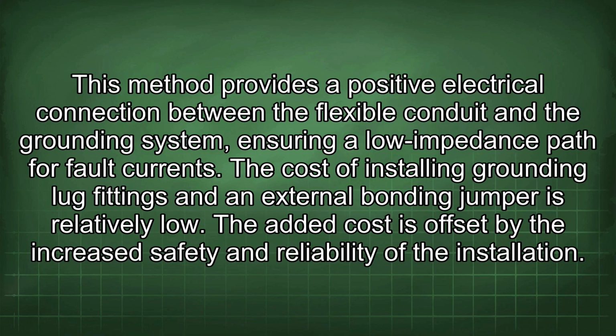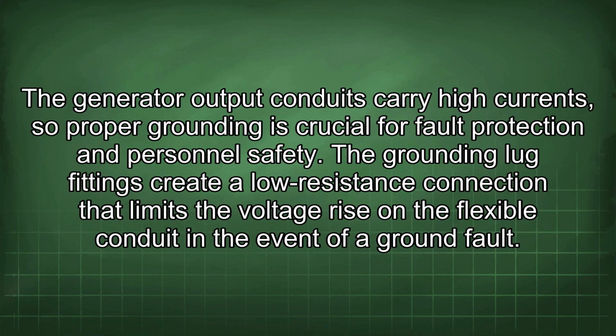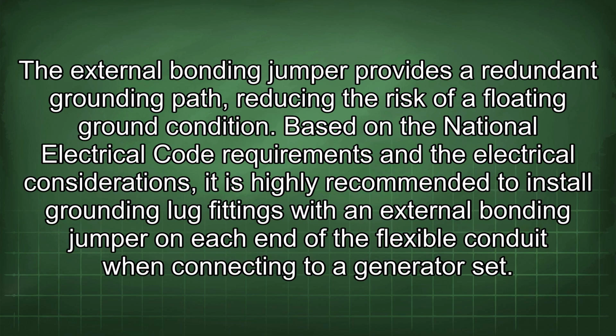This method provides a positive electrical connection between the flexible conduit and the grounding system, ensuring a low impedance path for fault currents. The cost of installing grounding lug fittings and an external bonding jumper is relatively low. The added cost is offset by the increased safety and reliability of the installation. The generator output conduits carry high currents, so proper grounding is crucial for fault protection and personnel safety. The grounding lug fittings create a low-resistance connection that limits the voltage rise in the flexible conduit in the event of a ground fault. The external bonding jumper provides a redundant grounding path, reducing the risk of a floating ground condition.